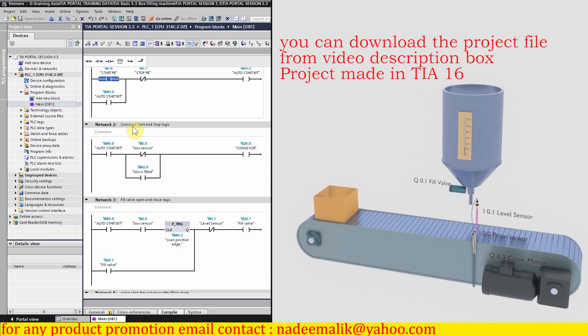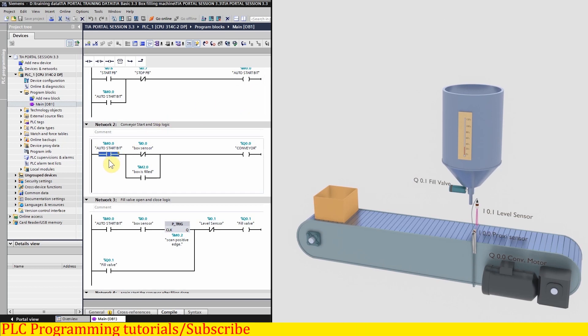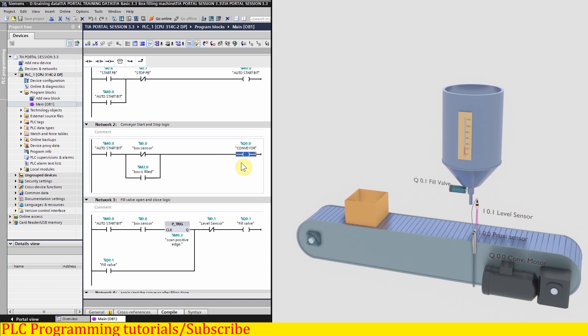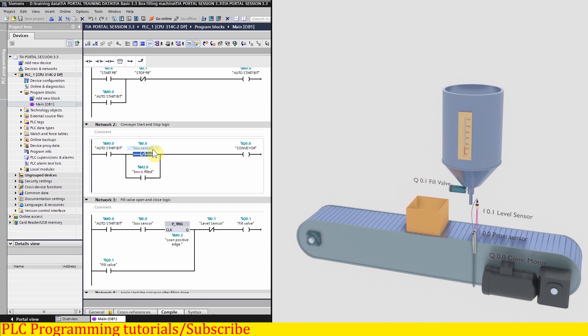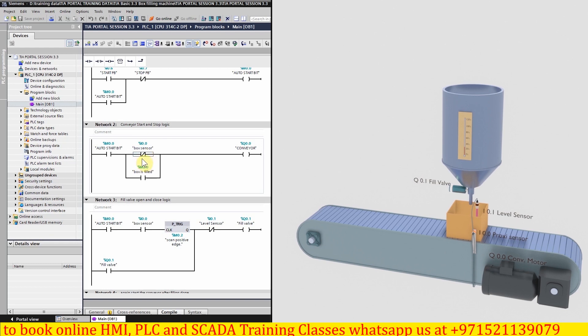In network number two we have the logic to start and stop the conveyor. We insert the auto start bit M 0.0 — whenever M 0.0 is on, it should turn on the conveyor Q 0.0. This conveyor should only stop when the box is present under the filling station, confirmed by the box sensor I 0.0. We use a normally closed contact, so whenever the box comes under the filling nozzle, it is sensed by sensor I 0.0, the normally closed contact opens, and it stops the conveyor Q 0.0.